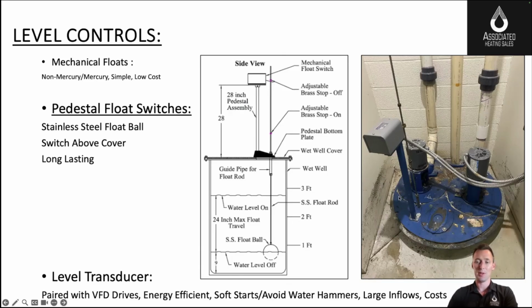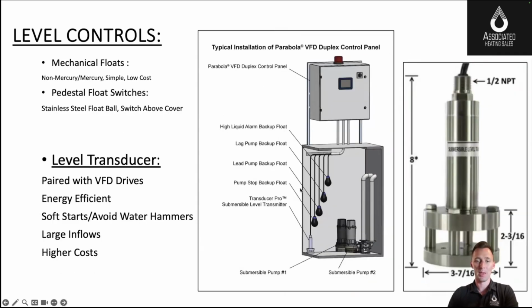Downsides, obviously, is you have to be in a mechanical room because this is sitting on the cover, which represents a tripping hazard, and you've got to have room for this in a mechanical room. But these would typically be coupled with our vertical pumps or a high heat system. Maybe you have submersibles, and this would be the best way to do controls. There's 4 positions for this switch above, and there's stoppers that actuate that. So it's a nice way to do it.